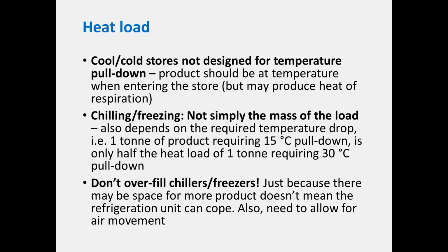the first job only has half the cooling load of the second. So the temptation for people is to look into their chiller or freezer or cold store and say, look, there's all that room, why don't we fill it up with product? But you have to recognize that it's not just the volume, the mass of the stuff in there, it's how much heat is in there. That's the most important message, which some people clearly have not received: you can't overfill chillers and freezers. Just because there is room doesn't mean you should put more product in.